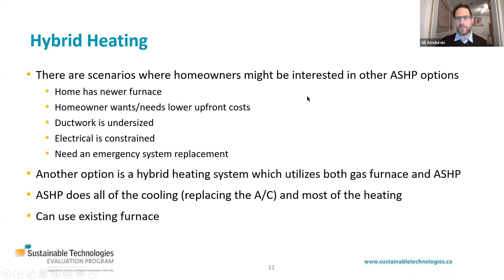Here's a bit more background. Hybrid heating can have lower upfront costs than fully electric systems, such as those cold climate air source heat pumps we mentioned before, but can maintain many of the benefits. The air source heat pump would be used for milder conditions, and the furnace for extremely cold conditions. In Southern Ontario, which is where this data is from, most of the heating energy is actually used in milder temperatures - extremely cold is actually very rare.